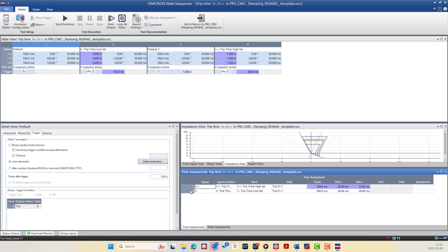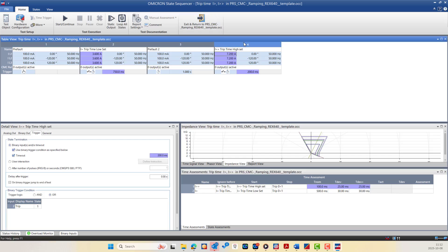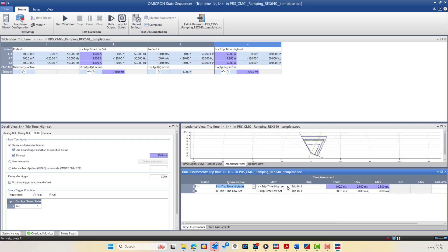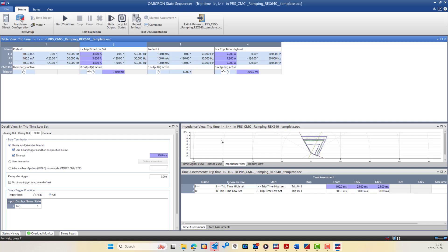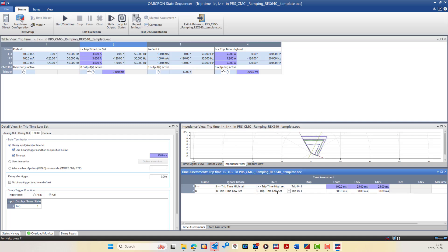You can define the criteria for evaluating the test result, specifically the expected trip time for each protection stage. For example, the first assessment expects the trip signal in 100 milliseconds for the high-set over current stage (I-double-greater), starting from state number four with the stop condition being the binary input trip changing from zero to one. For I-greater in state number two, the trip signal is expected to be 500 milliseconds. You can define the T-nominal and T-deviation (plus or minus tolerance) based on the relay technical specification, allowing automatic comparison of the measured T-actual against the expected value.